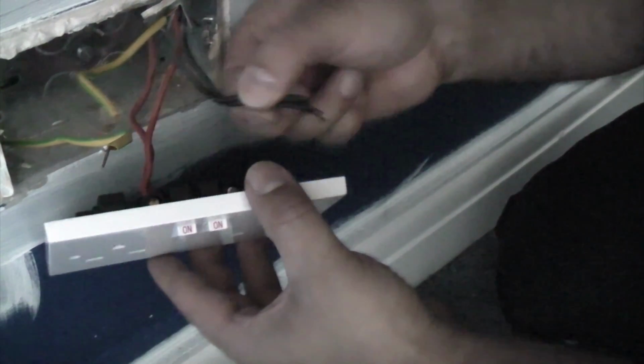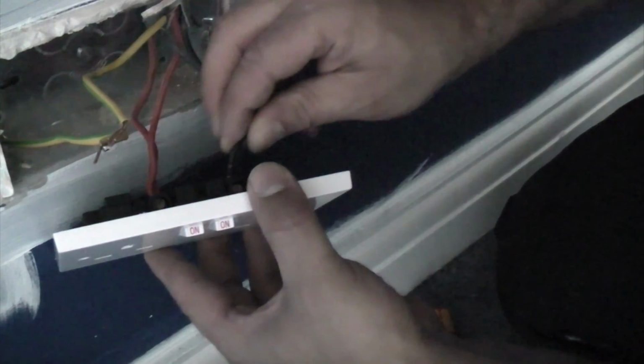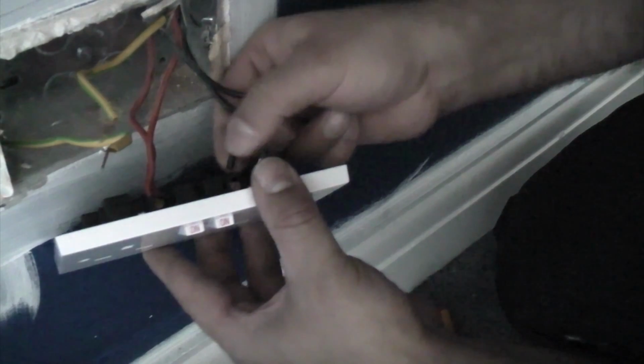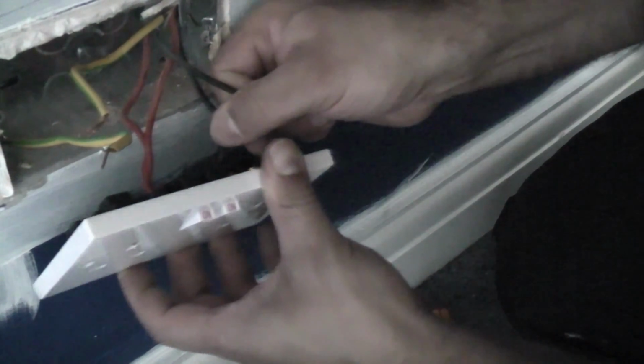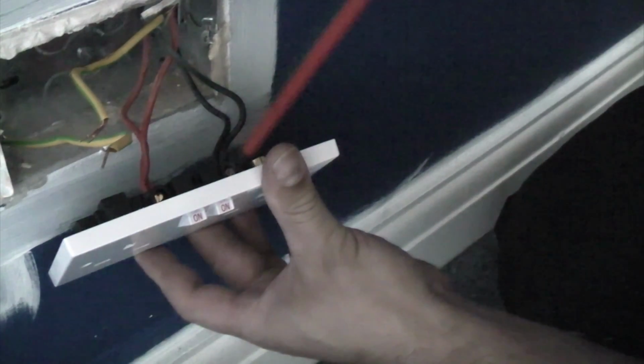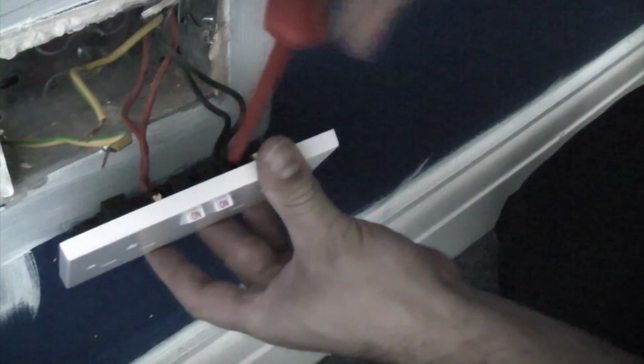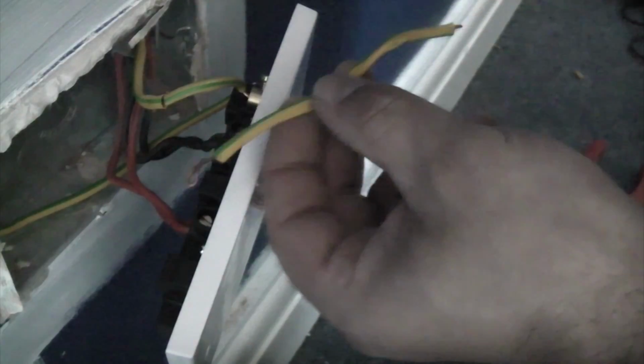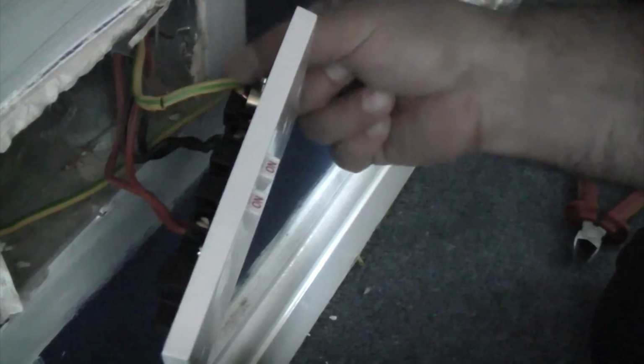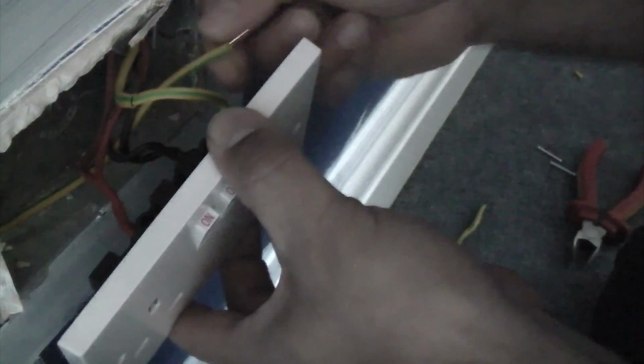So now we can put the 2 neutral wires in. When I've come to fit this socket, I've realised that the supplementary bonding wire isn't quite long enough, so I've actually fit a new piece, which is now there. So that goes directly to the back box and is fastened tightly. And now I'm just going to put that into that terminal with the additional 2 earths. And now I'm just going to tighten that up.